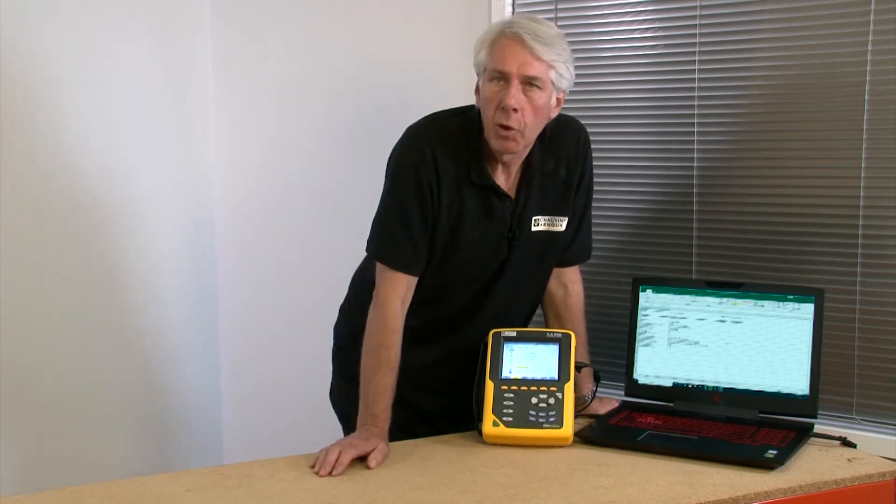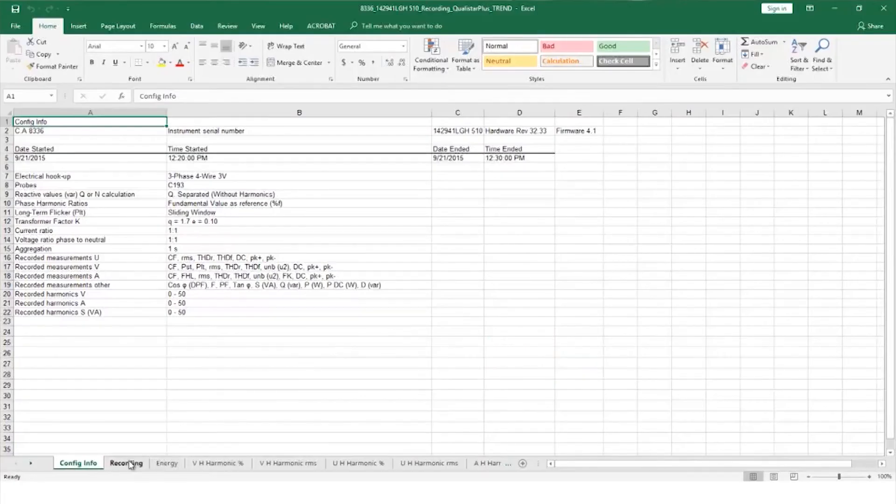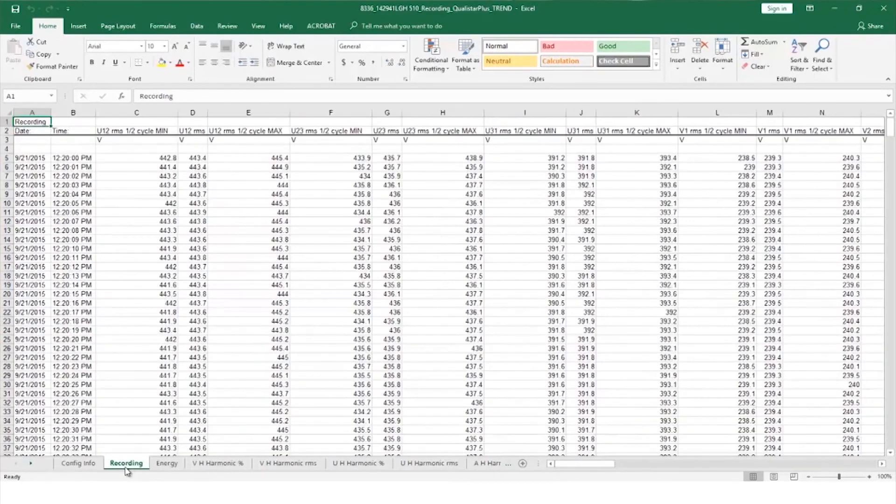Now when data is sent to a spreadsheet and opened in Excel for example, the Qualistar configuration is stored in one tab. The recording tab contains real in-depth information on all the measured currents and voltages over time with half cycle minimum and maximum information.